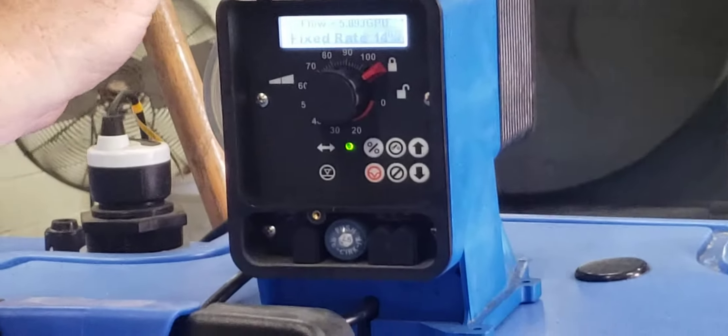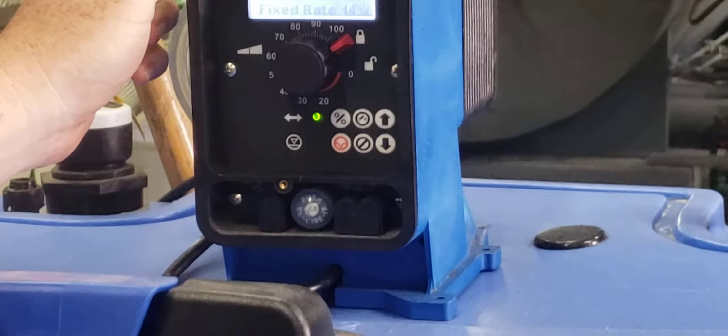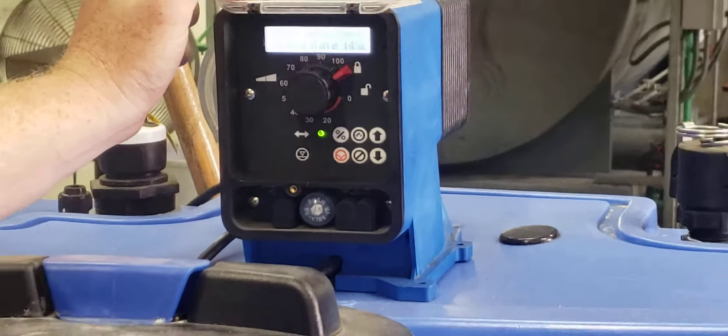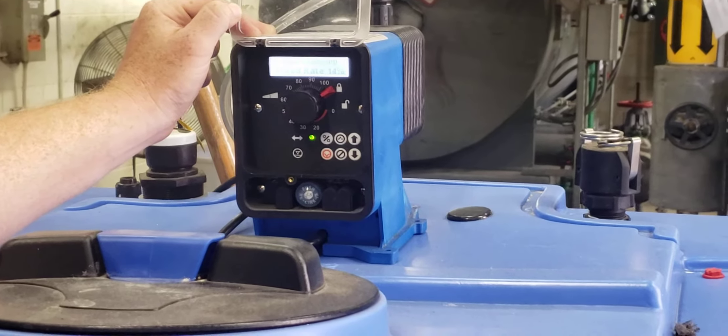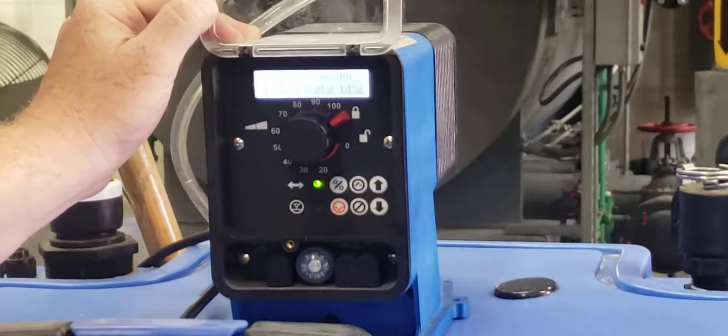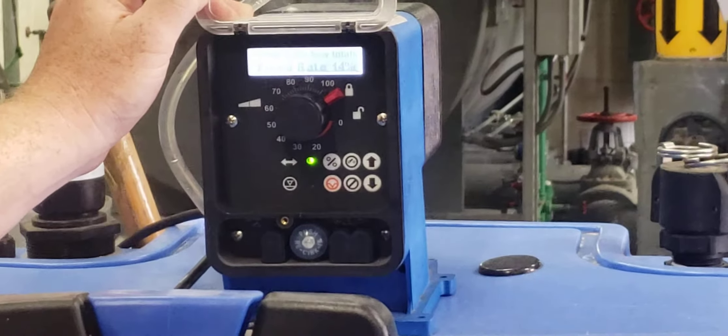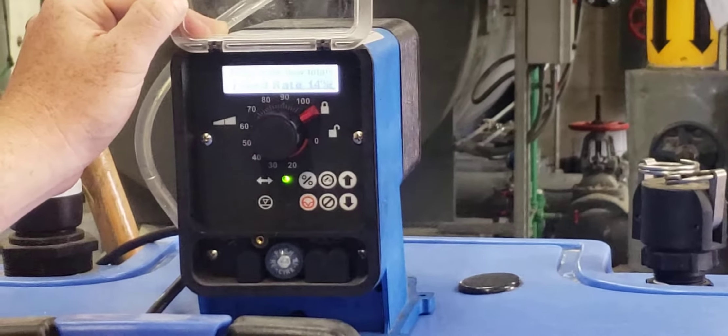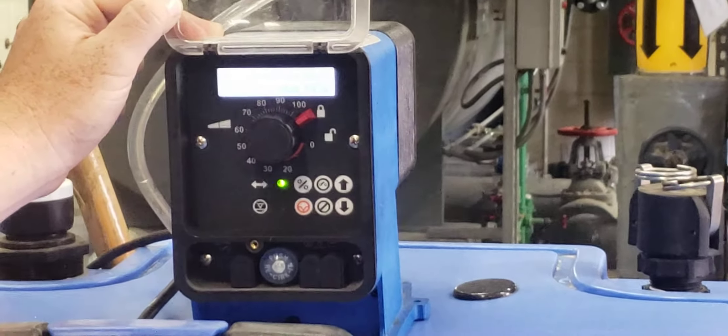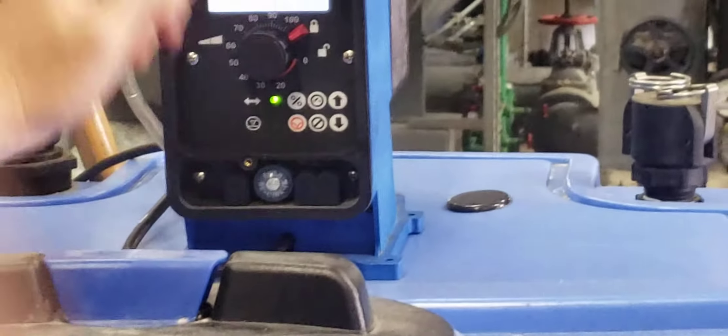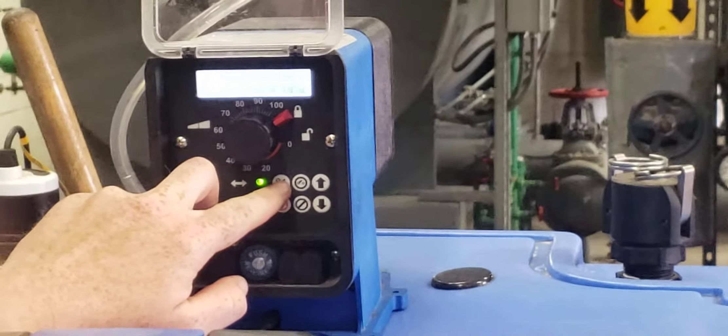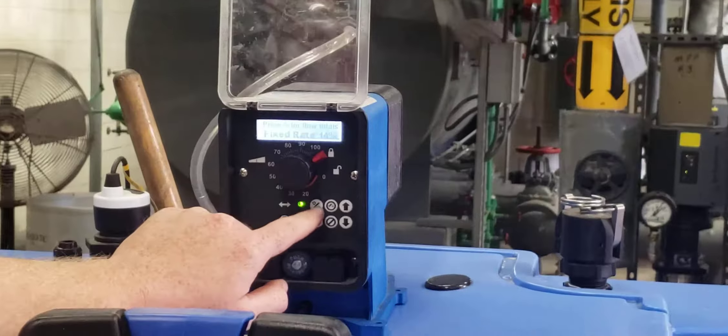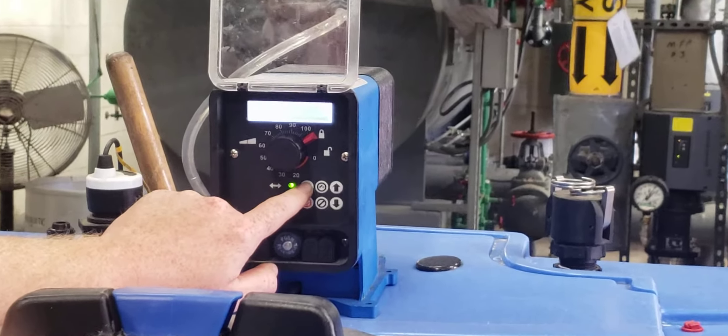From time to time, let's say you get a high sulfite reading or maybe a low sulfite reading, what's your corrective action? Your corrective action is going to be I've got to increase the feed of the pump. So I need to increase the percent in the feed. You're going to click the percent button.